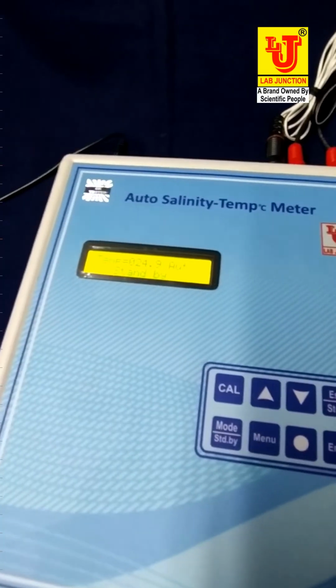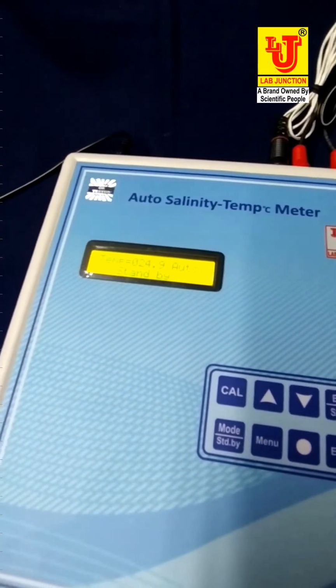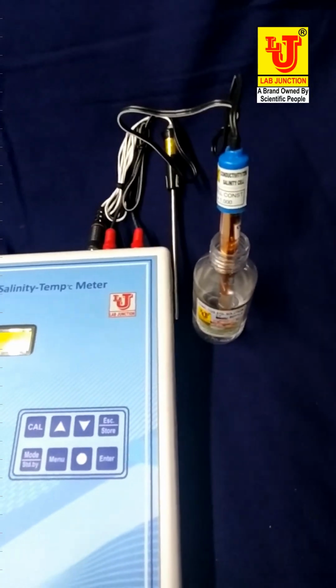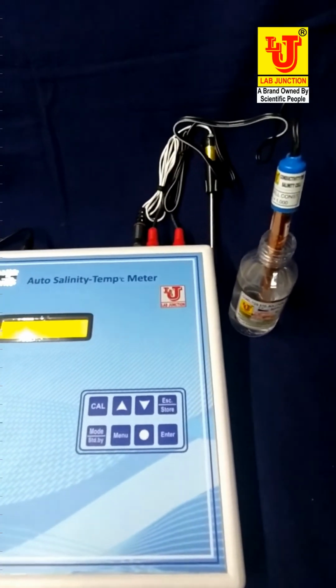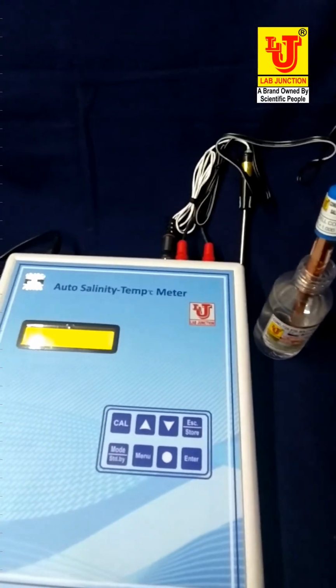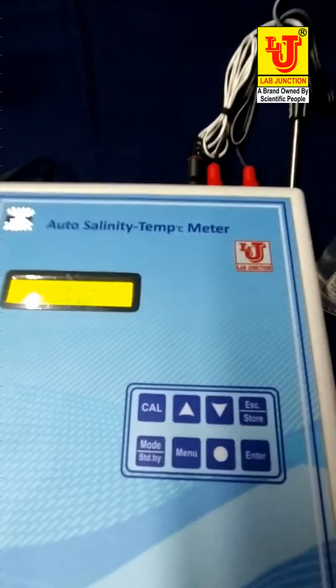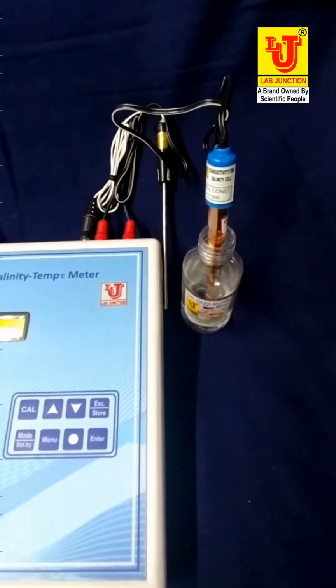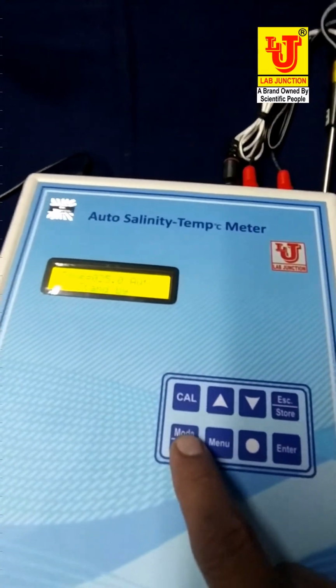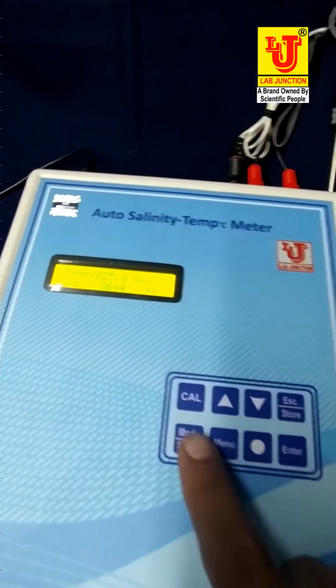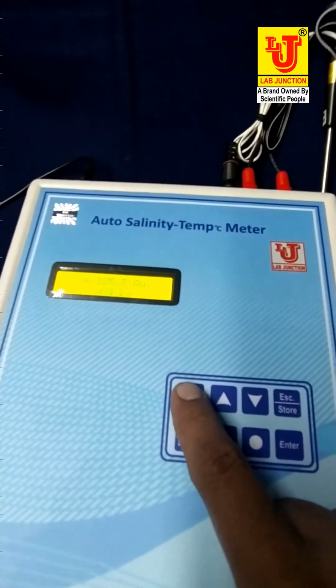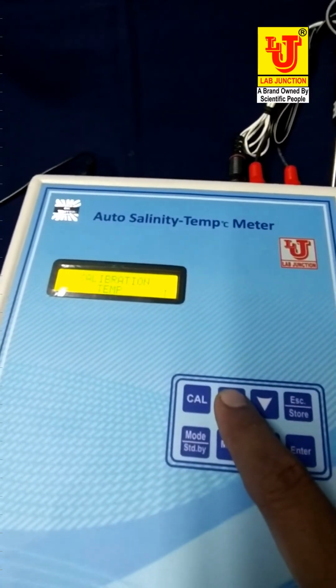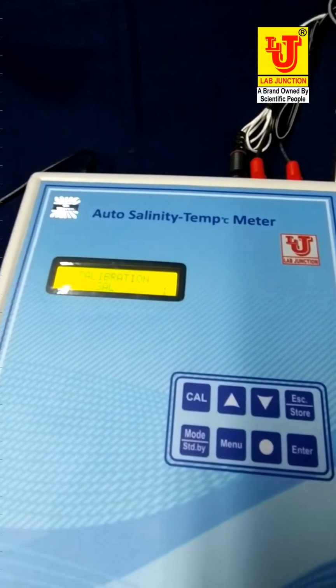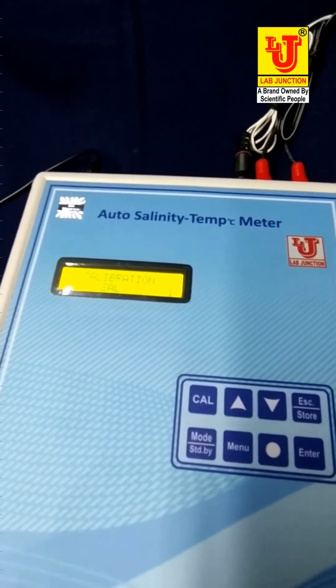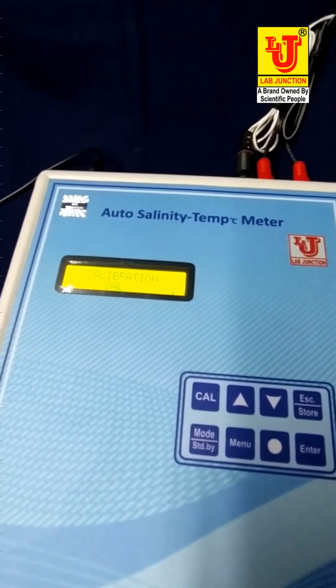Now how to calibrate this? Now I am dipping my salinity saline standard solution of 750 ppm like this. Now this is our main menu. This is analysis. This is main menu. Now press cal key. Bypass the temperature if your temperature is correct. Now on this option, calibration sal, it means calibration of salinity, press enter.